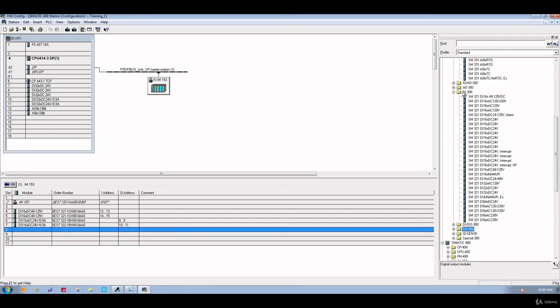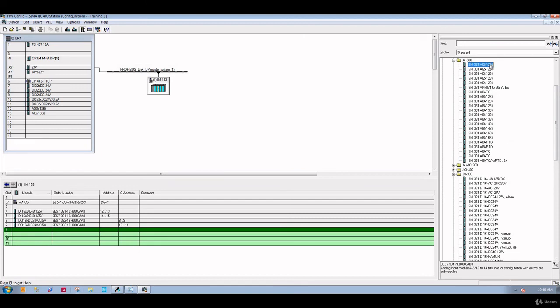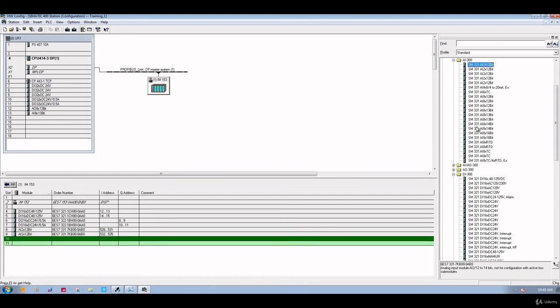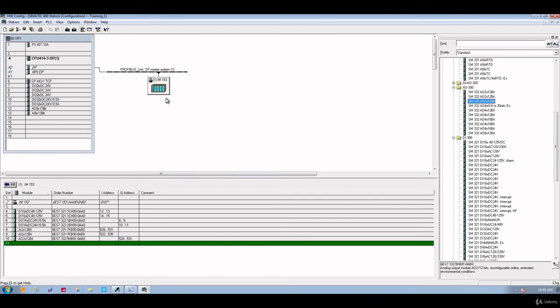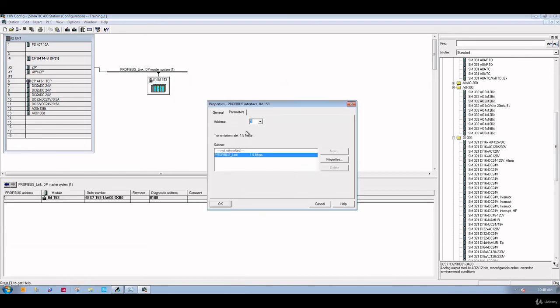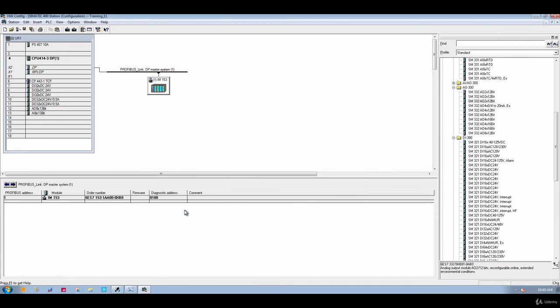and then use one of the analog input cards. Then there's two and one analog output card. This one, okay. And so now this is the first remote I/O. We can just copy and paste. Second one, it asks you for the next address, address 3, because address 2 is being used here. So this one, address 3, the next one, or you can select any of these addresses up to 125. So the network can take 125 remote I/O points, and press OK.